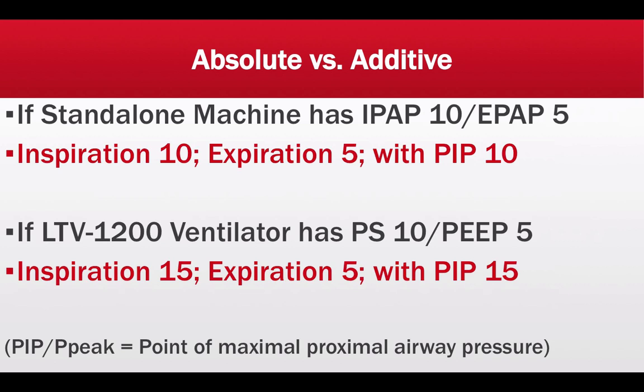However, on the LTV1200 and other ventilators capable of providing invasive modes, this is totally different. When pressure support is set at 10 and PEEP is set at 5, when the patient initiates inspiration, the ventilator will deliver 15 centimeters of water pressure — because pressure support is in addition to PEEP, so 10 plus 5 equals 15. Inspiratory pressure would be 15, and when the patient exhales, it will be 5 centimeters of water pressure.